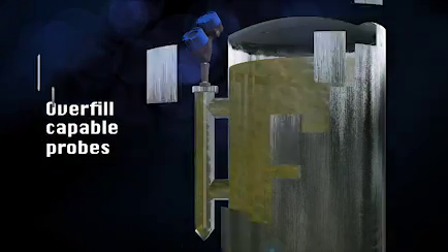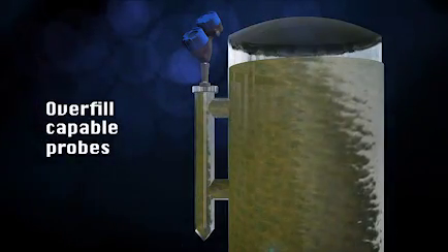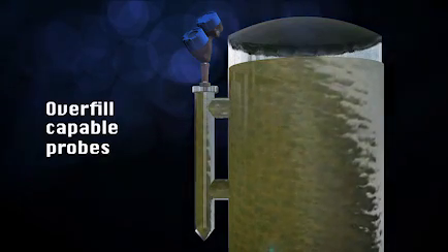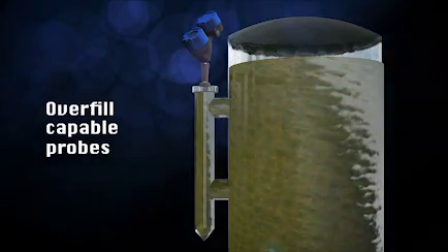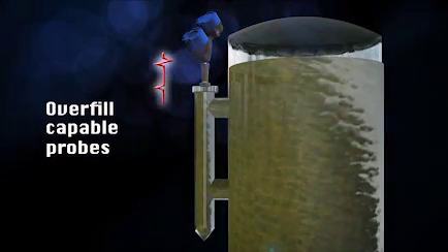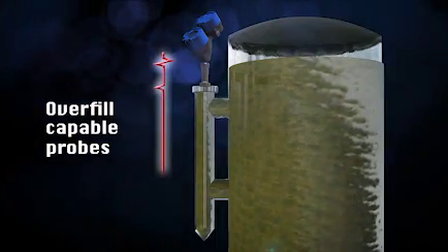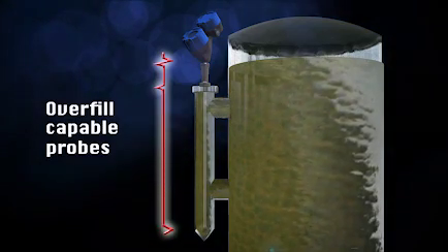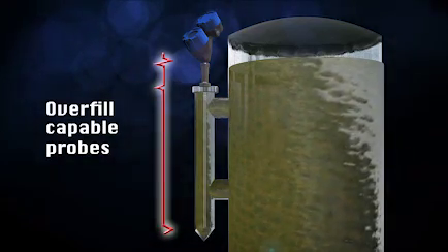The Eclipse Model 706 is the only guided wave radar transmitter on the market today with a full range of overfill capable probes. Unlike other GWR units that use algorithms to infer level readings in top of the probe dead zones, the Model 706 measures true level to within specification, all the way up to the process flange.